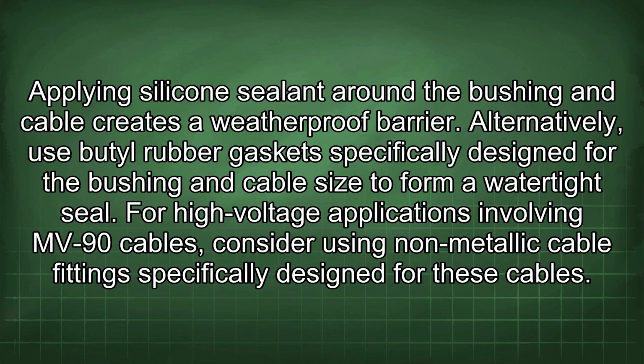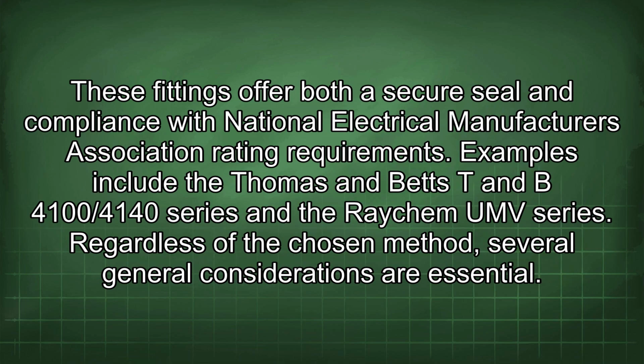For high-voltage applications involving MV-90 cables, consider using non-metallic cable fittings specifically designed for these cables. These fittings offer both a secure seal and compliance with National Electrical Manufacturers Association rating requirements. Examples include the Thomas & Betts T&B 4100/4140 series and the Raychem UMV series.